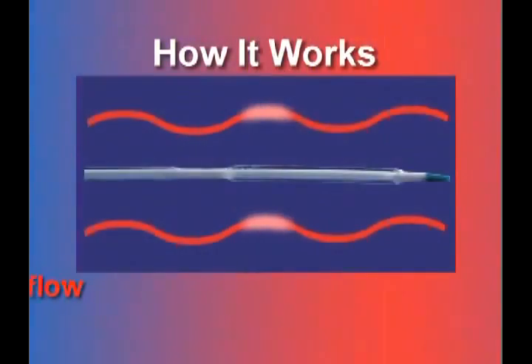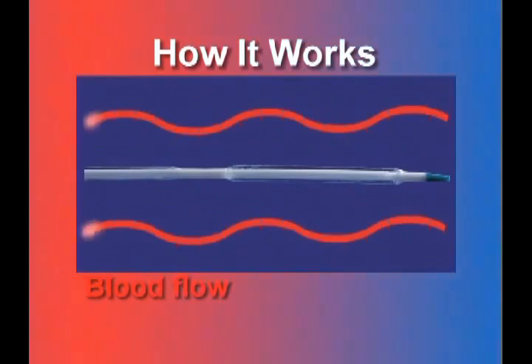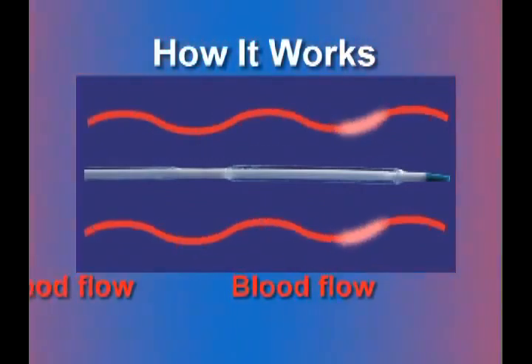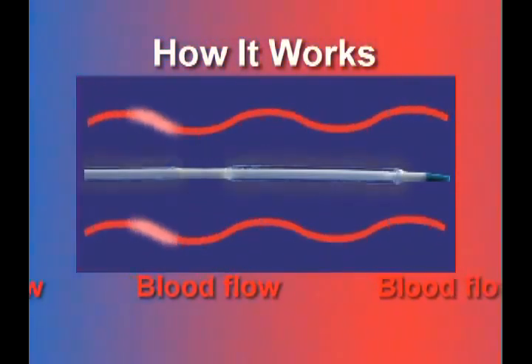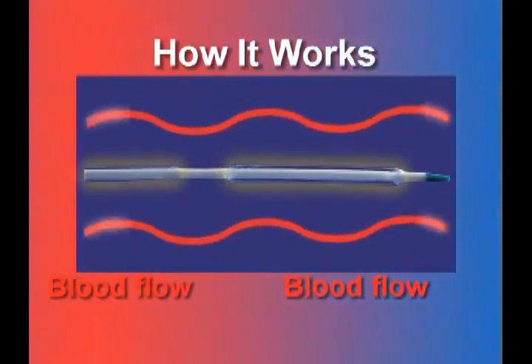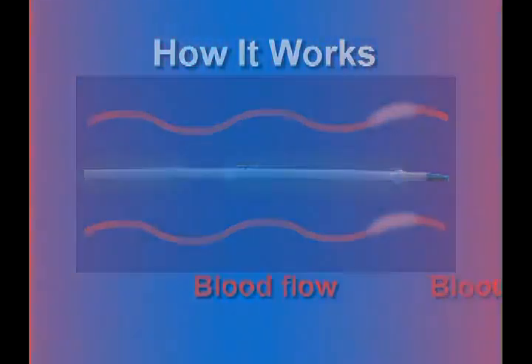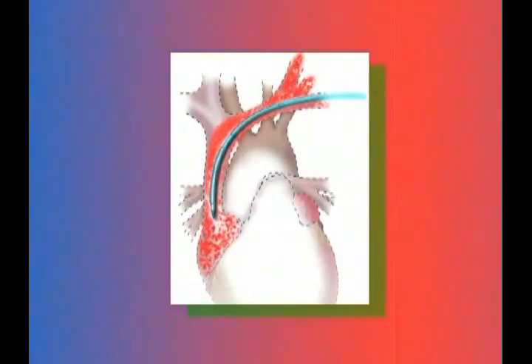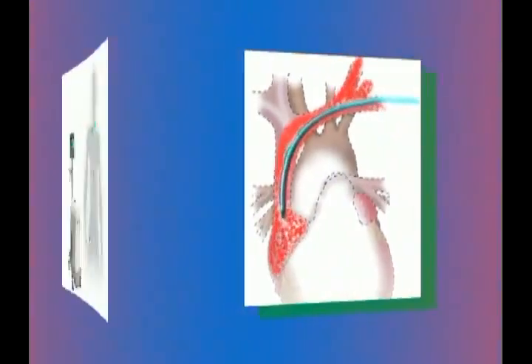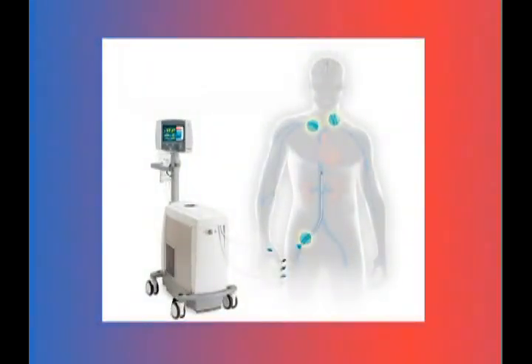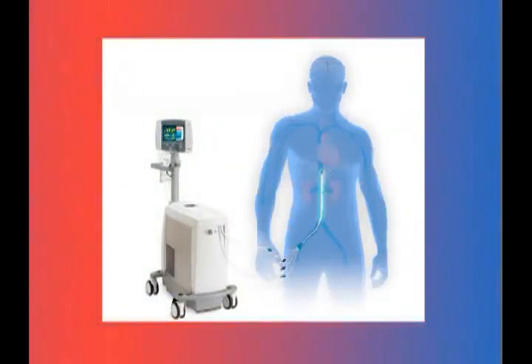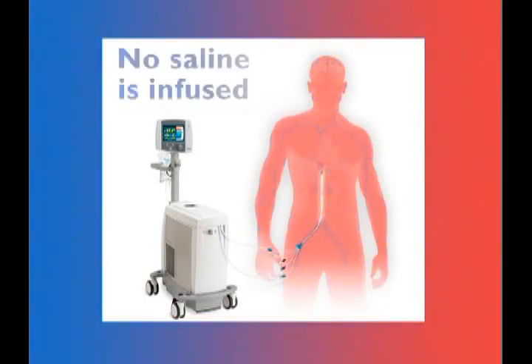How is this accomplished? Using a Zoll Thermogard XP system, temperature-controlled saline is circulated in a closed loop within balloons located on a central venous catheter. The Zoll system adjusts the temperature of the saline circulating within the balloons based upon the actual temperature of the patient. The patient's core temperature is then changed as the blood flows across the balloons on the catheter. No saline is infused into the patient, nor is any fluid removed from the patient.